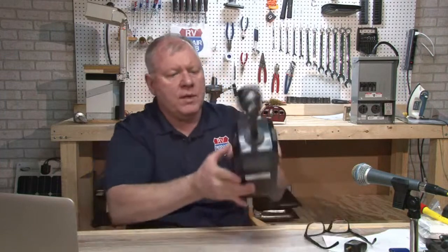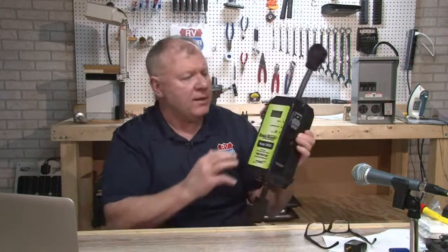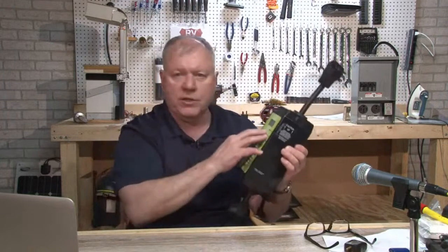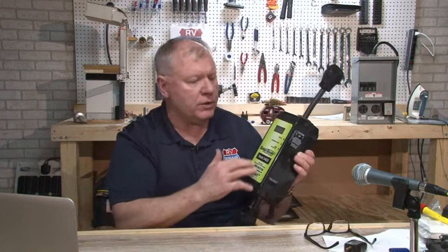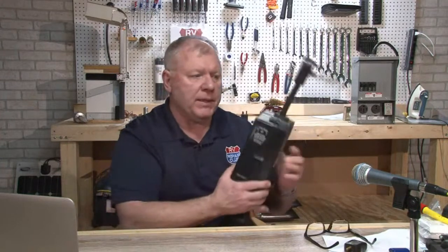See, this is the system we set up inside, and it's a little hard to see, but this shows I have 123 volts right here at my campground source too. And that's fine. You can go up, I believe, they say normally about 5% at least, so you can go to a high extreme with this. This is a surge protector that also guards against a high surge, but if it goes below voltage, you don't want to go below about 110, that's the lowest you want to go and still be able to run everything. Any lower than that, everything runs sluggishly and you'll have problems with motors, capacitors, air conditioners and other things. But you should be fine.